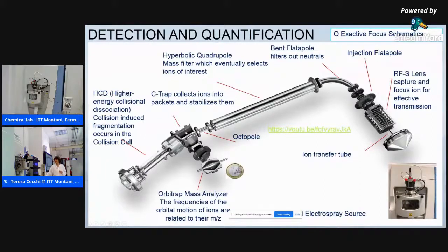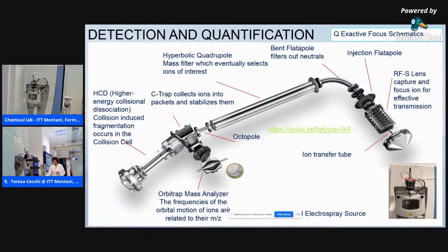Then we have a C-trap which collects ions into small packets and stabilizes them. And then these packets are injected into the mass analyzer, into the orbitrap, where the frequencies of orbital motion of ions are related to their m/z ratio. The Fourier transformation enables us to go from the time domain to the frequency domain and then to the m/z values. Eventually, we may have a collision cell where collision-induced fragmentation may occur if we decide to fragment specific ions that were previously detected in the full scan mode.